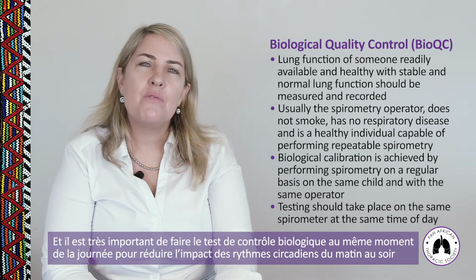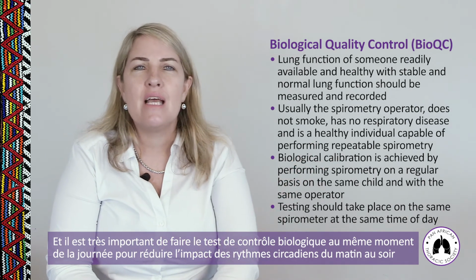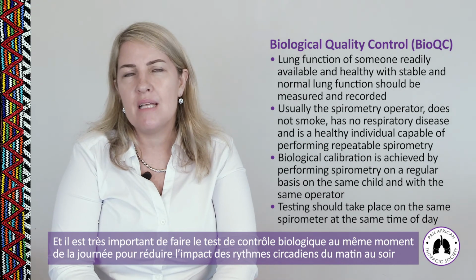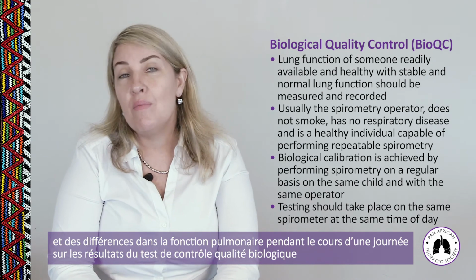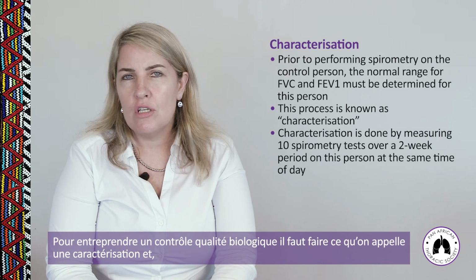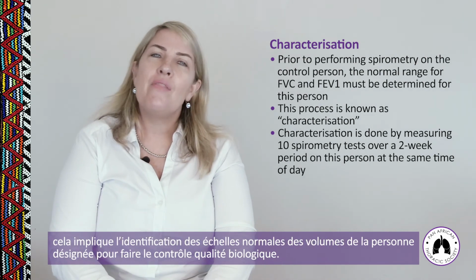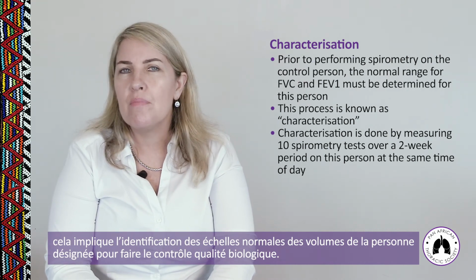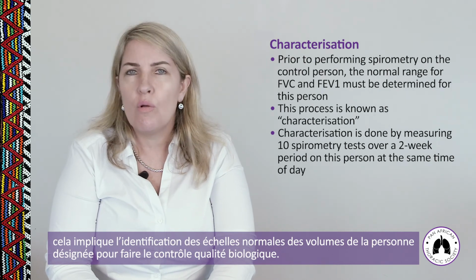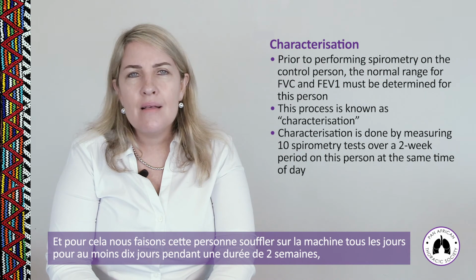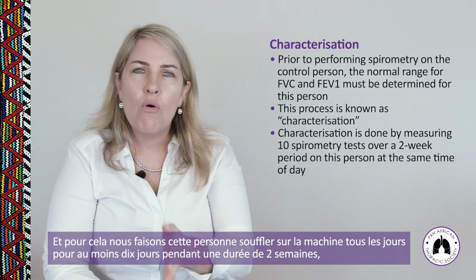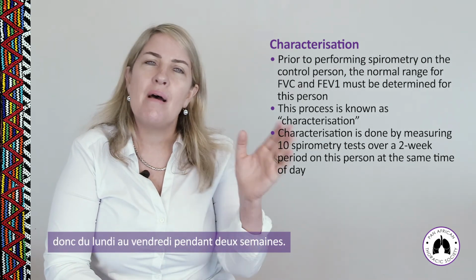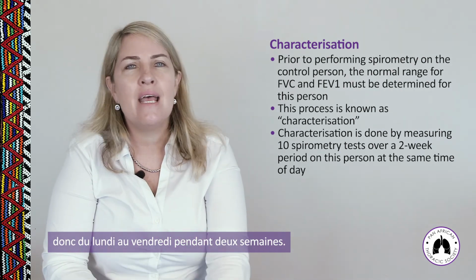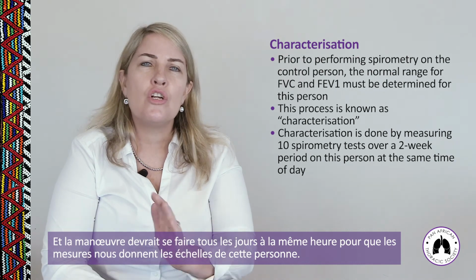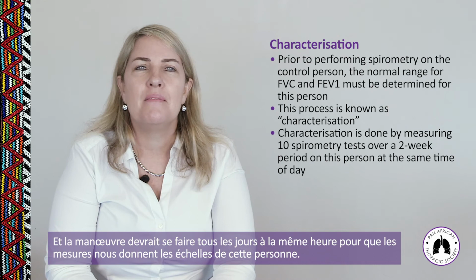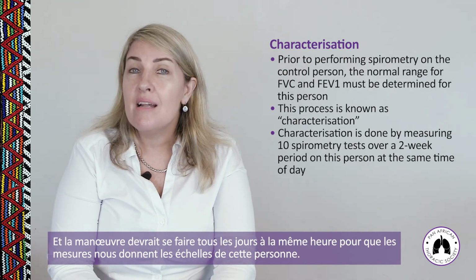And it's very important that we do the biological control testing at the same time of day to minimize the effects of circadian rhythms and differences in lung function from morning to evening when we are doing biological calibration itself. So to do a biological calibration, what we need to do is what we call characterization. And that is finding out what are the normal ranges of volume for the specific biological quality control person. And the way we do this is we get the person to blow onto the machine every day for at least 10 days over a 2-week period. So from a Monday to a Friday, 1 week, and then the second week a Monday to a Friday, this biological quality control person should blow onto the machine every day at the same time of day to be sure that they are measuring so that we can get the ranges allowed for them.